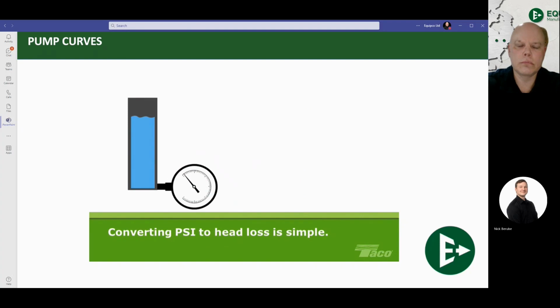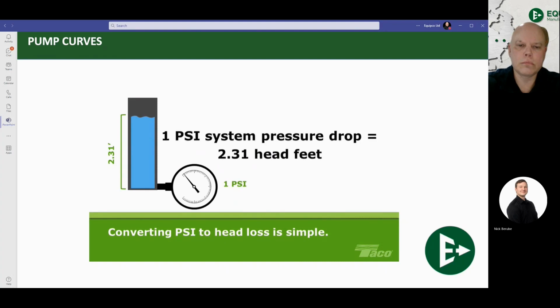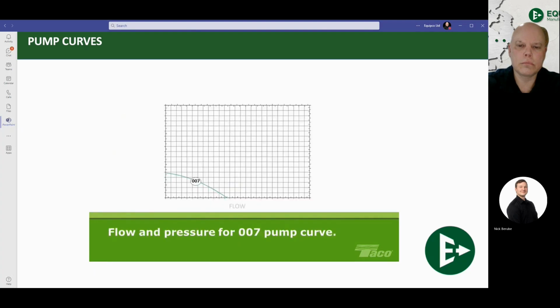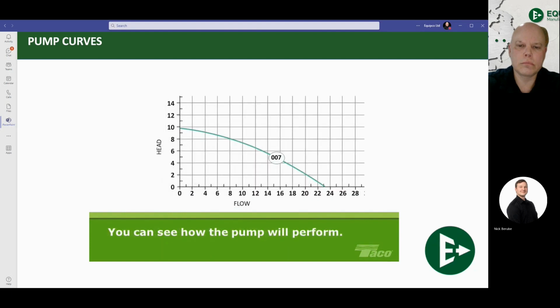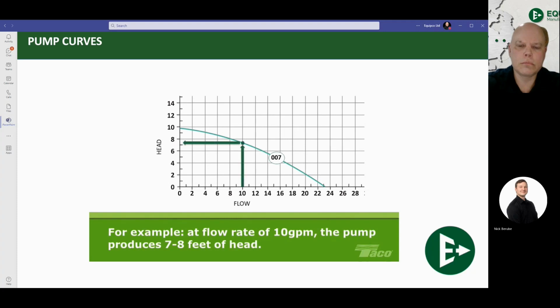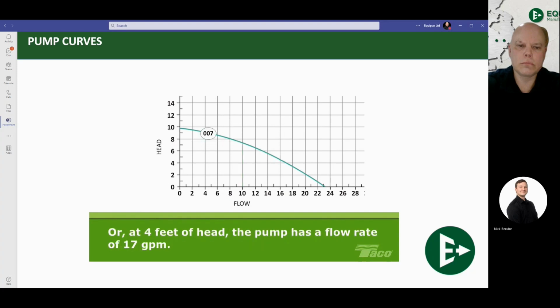Converting PSI to head loss is very simple. A column of water 2.31 feet or 28 inches high will have a gauge pressure at the bottom of 1 psi. Therefore, 1 psi of pressure drop in a system equals 2.31 feet of head. Let's see how these two factors look on a pump curve graph. The curve enables you to see how this pump will perform at any given point within its performance range. You can see, for example, that at a flow rate of 10 gallons per minute, the pump will produce between 7 and 8 feet of head. Or you can look at it the other way around. At 4 feet of head, this pump will generate a flow rate of just about 17 gallons per minute.